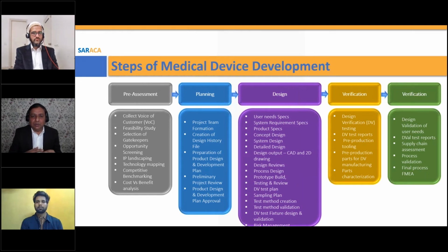Many times you make these risk management files and you only look at them when you get post-market surveillance data, either proactive or reactive, and if you have an incident which triggers an update to the RMF, then only you will update your RMF. But that's no longer accepted now. You will have to look at your risk management file, keep continuing based on your internal audit, external audit, or any change you see in your process or your proactive or active post-market surveillance. You will have to come back and keep updating it to ensure that it is safe and effective.